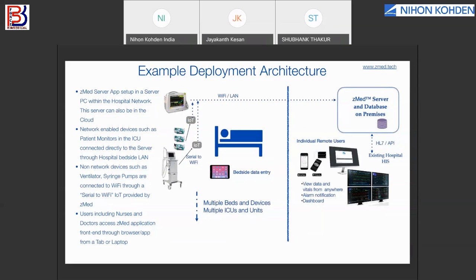You would leverage IoT, basically Internet of Things, Wi-Fi and LAN network to communicate to these medical devices. Since most of you are biomed engineers, you should be aware that almost all medical devices from any standard manufacturers have something called a data interface protocol. So patient monitors, either it be Nihon Kohden or Mindray or Philips, they all have these data interface mechanisms through which data can be exported to a third-party application.